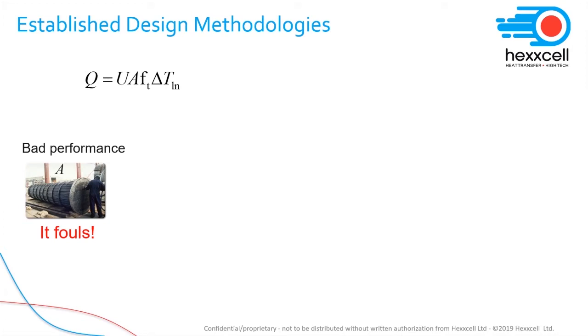The way fouling is typically accounted for is by adding a certain fixed number, the fouling factor, that accounts for an additional resistance to heat transfer in the overall heat transfer coefficient. These numbers are available in the literature, for example from TEMA, the Tubular Exchanger Manufacturers Association, or provided to the designer by corporate guidelines. Very often, these fouling factors are used because they are perceived in industry as safety factors that prevent the heat exchanger from degrading its performance over time. However, when introducing these fouling factors in the overall heat transfer coefficient, U decreases, and since we still need to deliver the same heat duty as before, we now need to have a bigger area and therefore design a bigger heat exchanger.